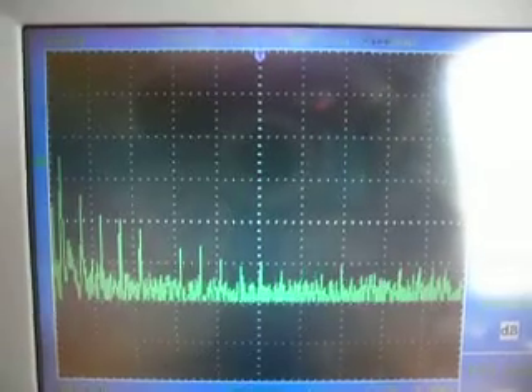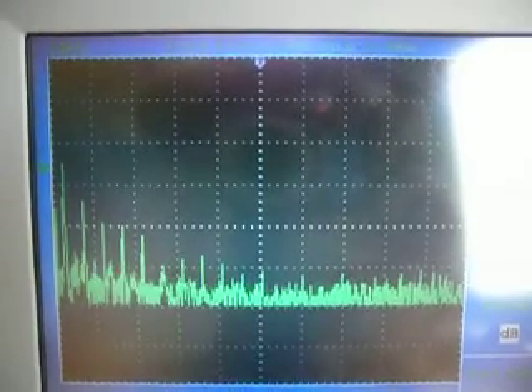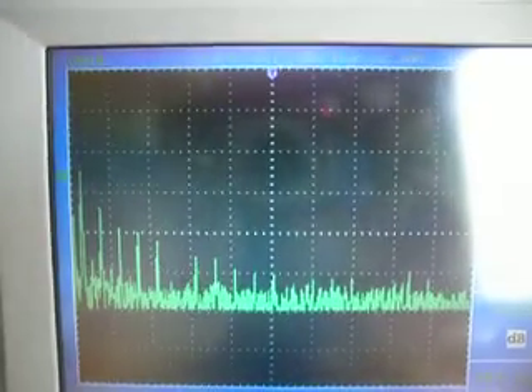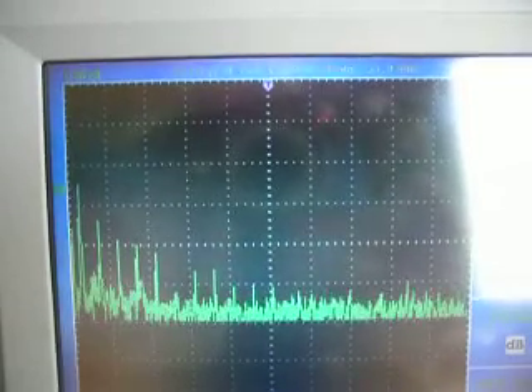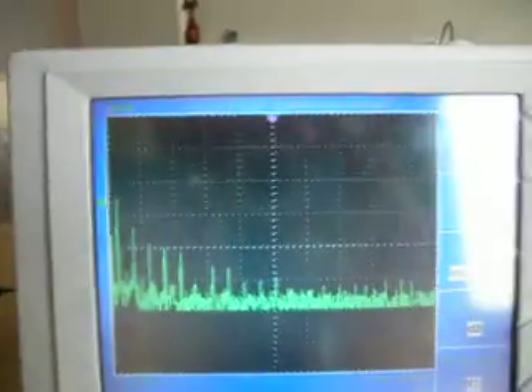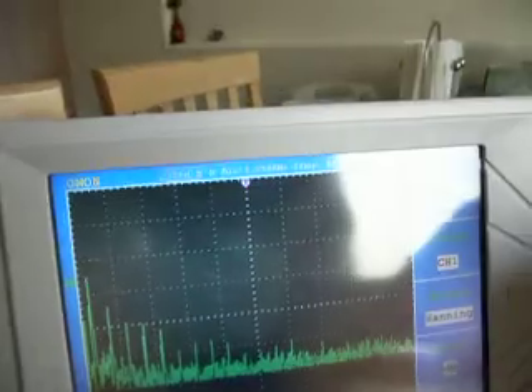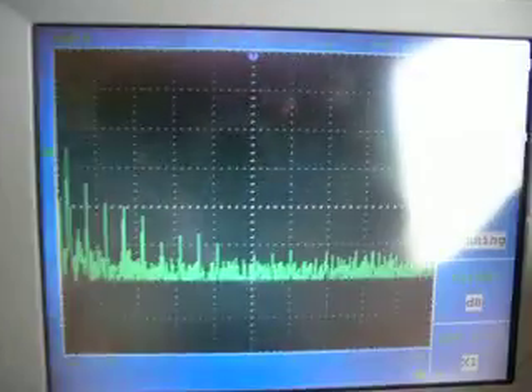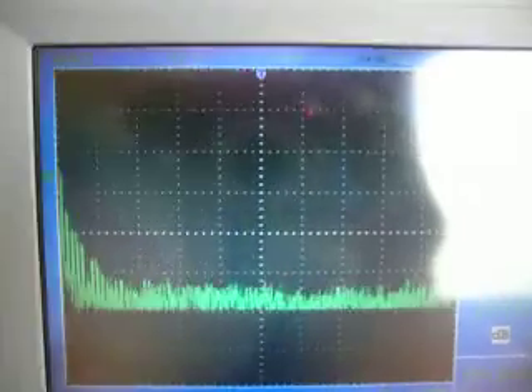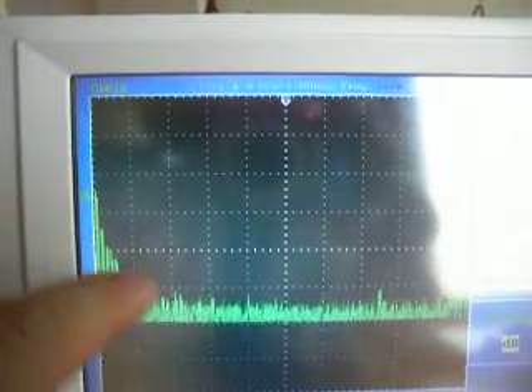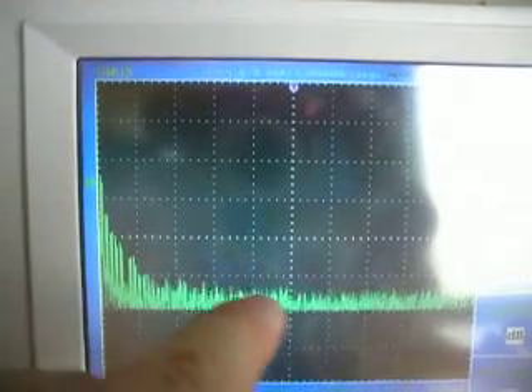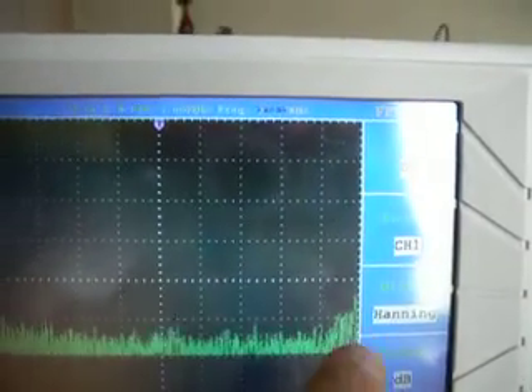I'm going to extend out the frequency because there's far more frequencies in there. Right now we're on 250 Hertz per division, let's see what happens when we go to a kilohertz. Now on a kilohertz, we can see the harmonics are condensed into here. We've got a lot of noise, but it's starting to spike up again.